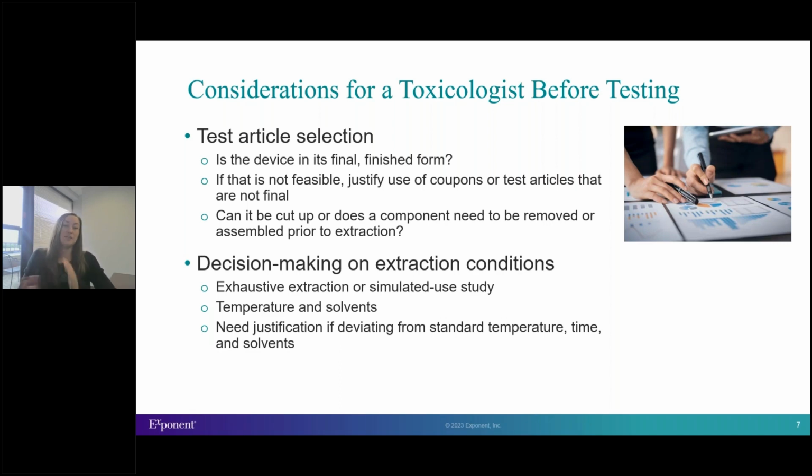So is it an exhaustive extraction study? Are you trying to get more at a simulated use, more clinically relevant leachables test? That's going to impact the temperatures, the solvents, and other parameters that are selected for the extraction conditions. And if you're deviating from standard temperature, time, solvents from what's used typically, you often need to provide justification, whether that's ahead of time to the agency that you're dealing with or on the back end if changes need to be made. And as toxicologists, we can certainly help with this.